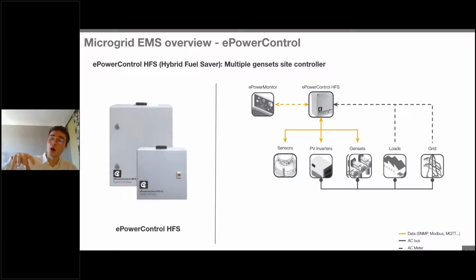Then we will also be connected to all of the different gensets to be monitored and controlled on site. Those gensets are integrated again over Modbus communication, but for some specific sites, for some specific reasons, you don't have the right to connect to those gensets directly. We can also monitor them through power meters and control the PV inverters according to that monitoring of the genset made by the power meters. So again, we have this cross compatibility with different site typologies and different site constraints on the genset side.